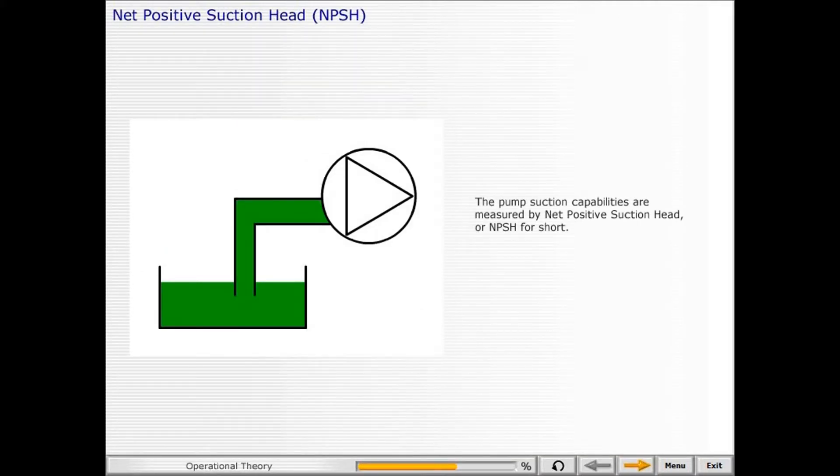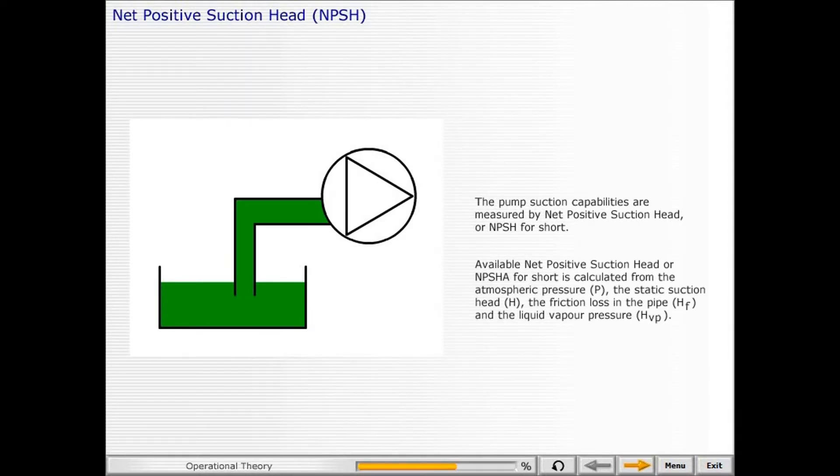The pump suction capabilities are measured by net positive suction head, or NPSH for short. Available net positive suction head, or NPSHA for short, is calculated from the atmospheric pressure, the static suction head, the friction loss in the pipe, and the liquid vapor pressure.